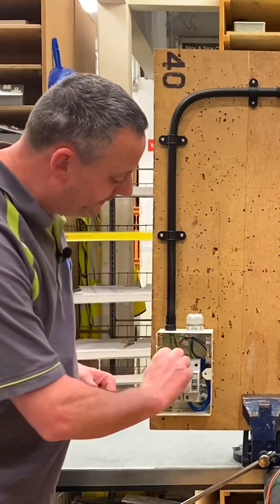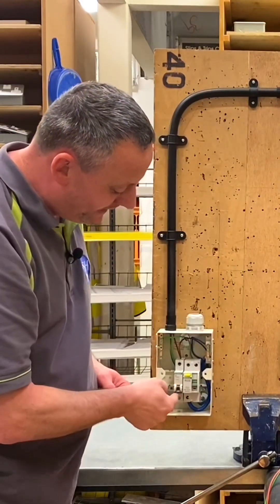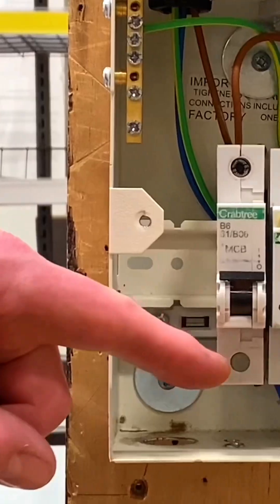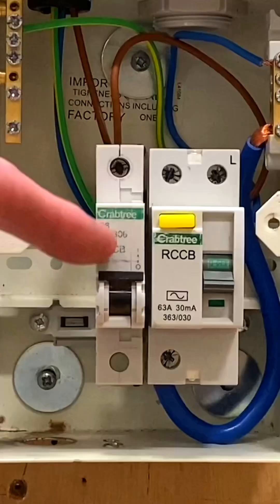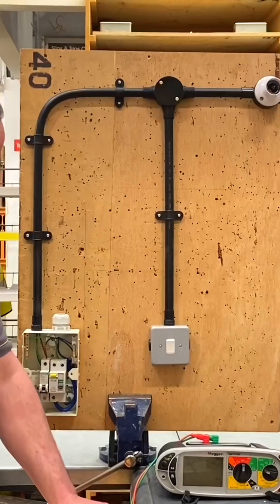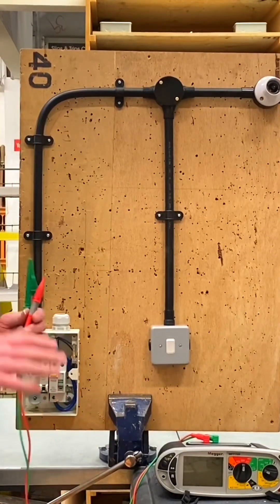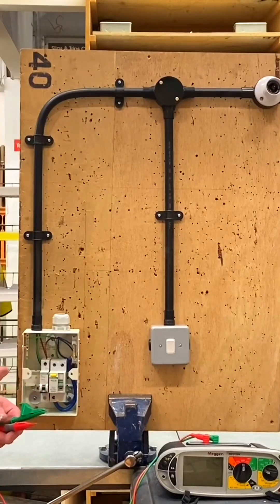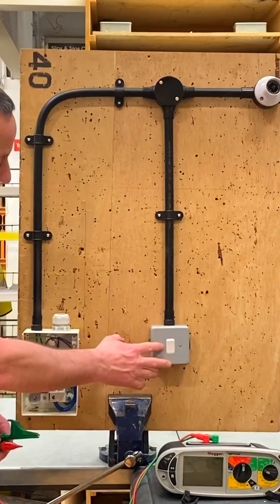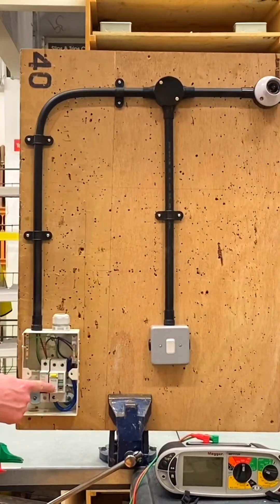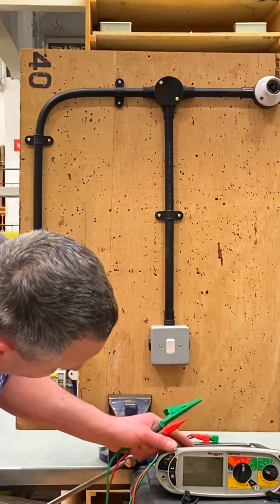The RCCB needs to be off because there are electronic components in there that will be potentially damaged by the 500 volts DC. We always leave our circuit breaker off - even though it doesn't have electronic components, the test tests outwards but also tests down. If we left our breaker on, the 500 volts would pass through and across the bottom of the RCCB which does have electronic components. I know you're a bit further away for this test, but we've done it many times on the channel.